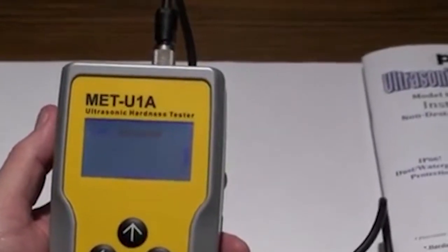If you press the right arrow button, you'll scroll through to HRB. This is used for aluminum. HV, again, is used for steel. HB, which is Brinell, is also used for steel.